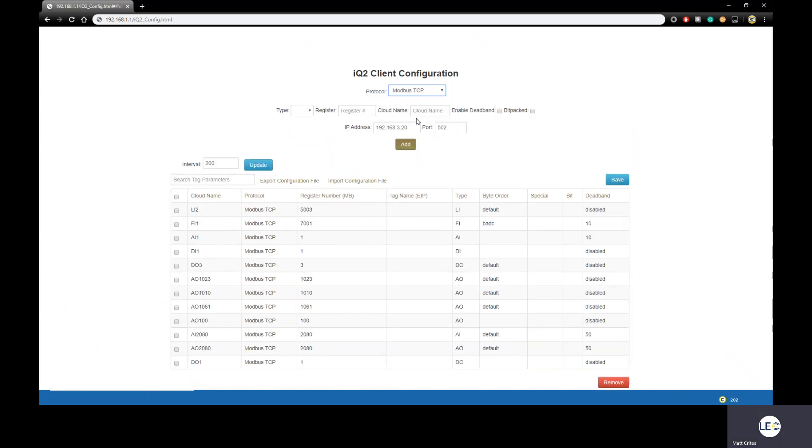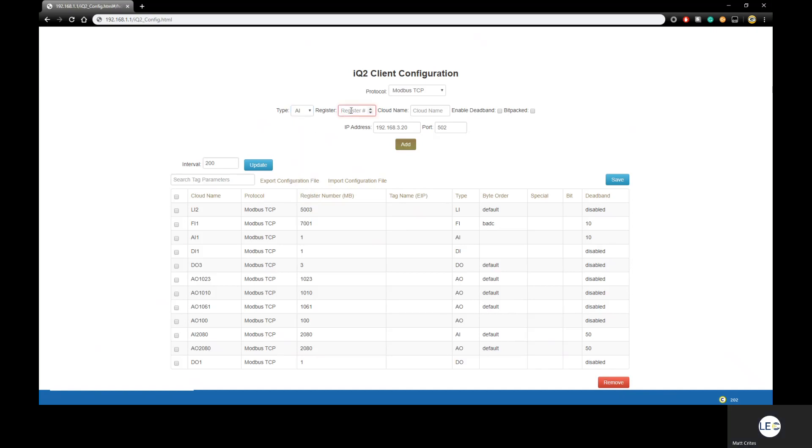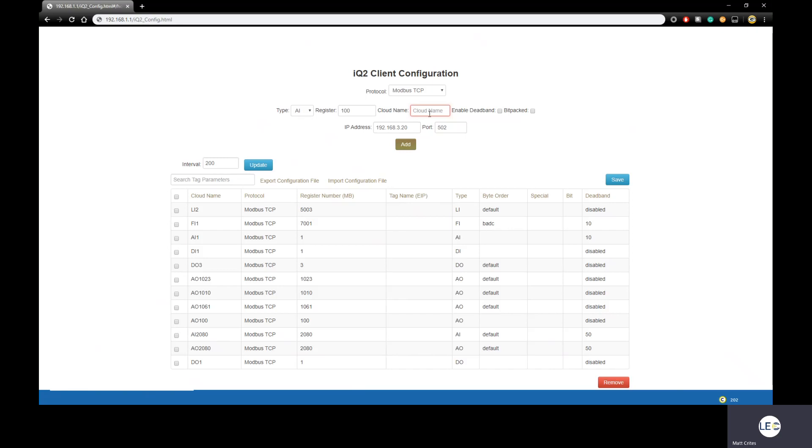Once the protocol is selected, a new set of fields will appear on the screen. We first must select the type. What are we configuring? Is it an analog? Is it a digital, a long, or a float? In this example, I'm going to choose analog input. Next, enter the register number, whatever that may be. The next thing we need to enter is the CloudName. The CloudName is how IQ2 maps registers to its database. The CloudName must match the type and register chosen. So in this example, I have chosen a type of AI and a register of 100. So my CloudName will be AI100.